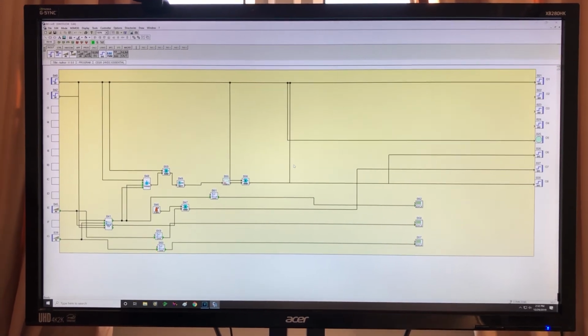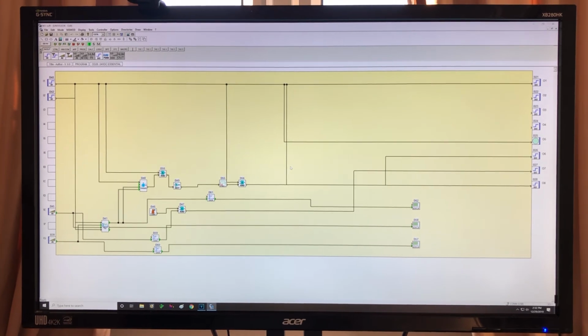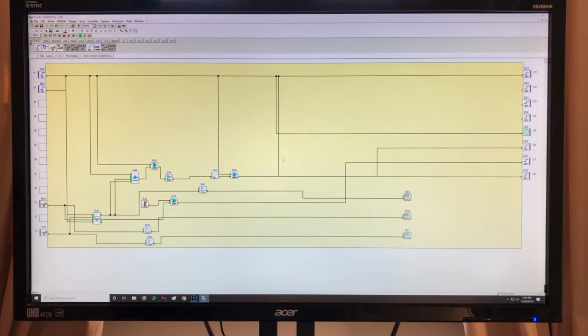Now, as you will see on the left hand side, I have inputs, on the right hand side I have outputs. What is in between? It is your concept. So it's very important to understand control. Just imagine you will build a plant room, and what you see are boilers. I've got boiler number 1, boiler number 2, and finally boiler number 3. So I chose to have 100% total capacity provided by 3 boilers. If one fails, at least I have 66% of the capacity.